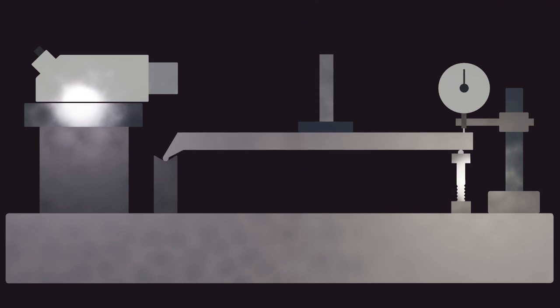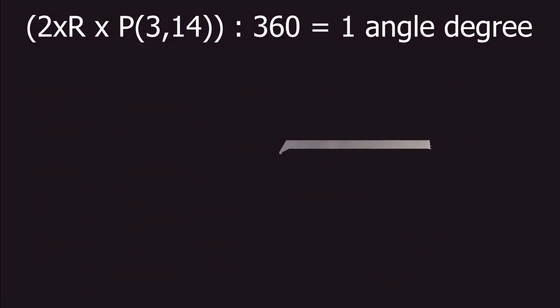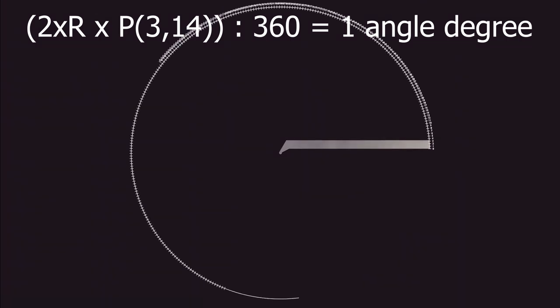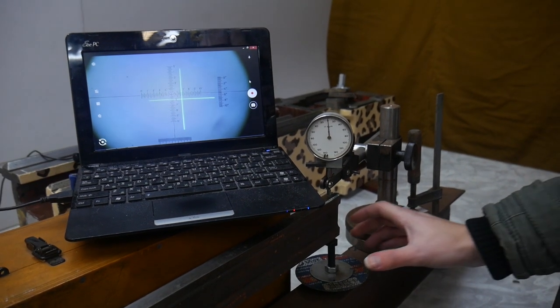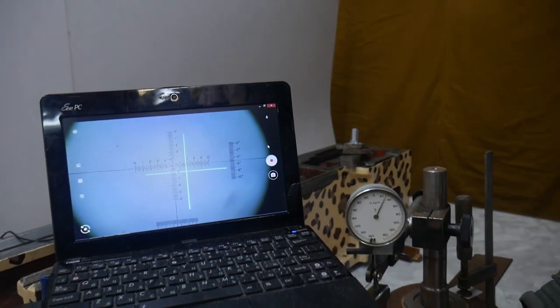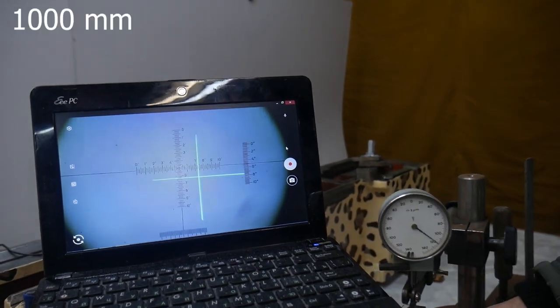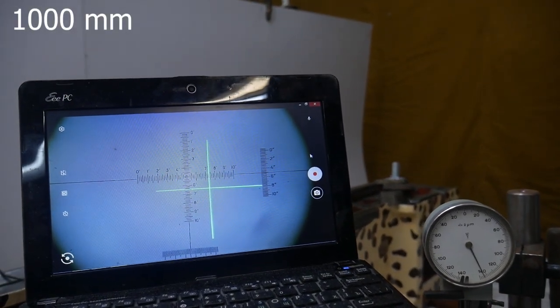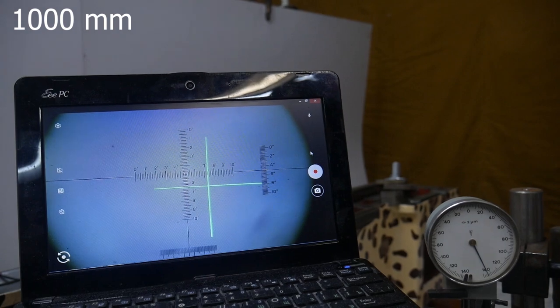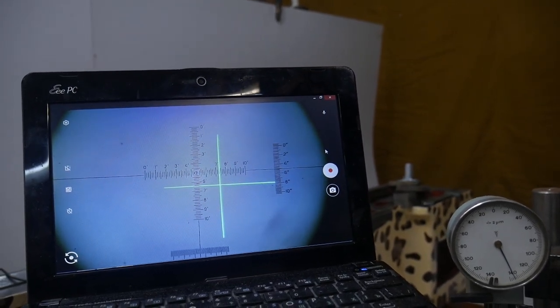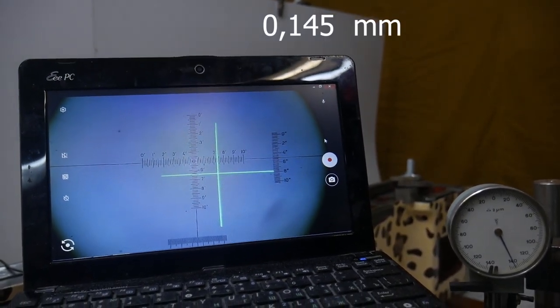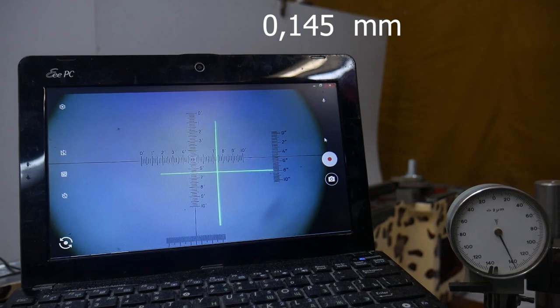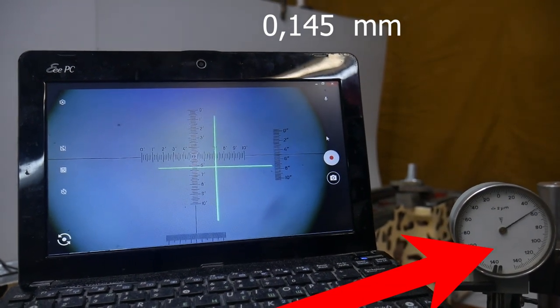The stand is set up like this. It is not difficult to calculate the height of movement corresponding to one degree. One degree divided by 60 is one minute. One minute divided by 60 is one second. The platform is 1000 millimeters. The left edge is the center of rotation. I raise the right edge by 145 microns.